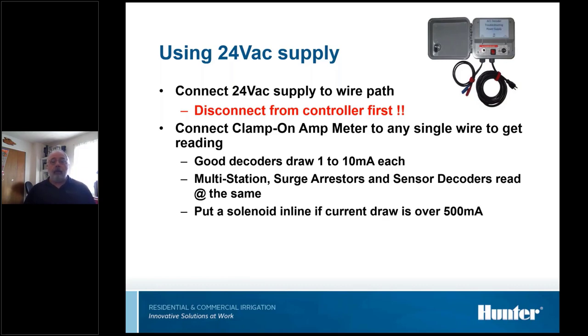Now, the way you do it, if I see a current draw over 500 milliamps, even with my big power supply, I put the solenoid in line. It's just a safety thing at that point. I've seen them draw four amps before. That's tremendous. 4 amps can catch stuff on fire. It's dangerous. I've literally seen the ground wire on an ICD decoder melt right through a piece of poly when it was drawing high amperage like that. So like I say, if I see over 500 mils, I put a solenoid in line.